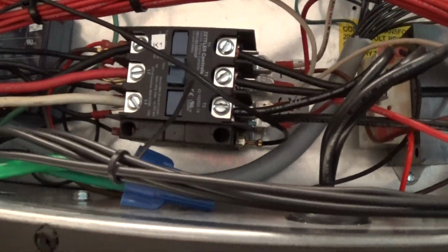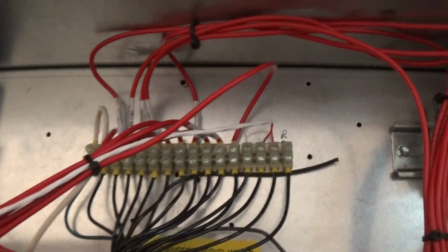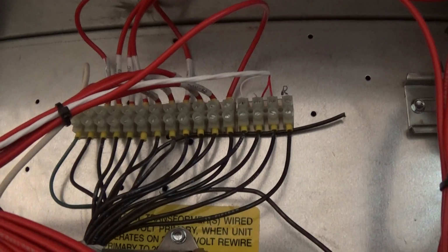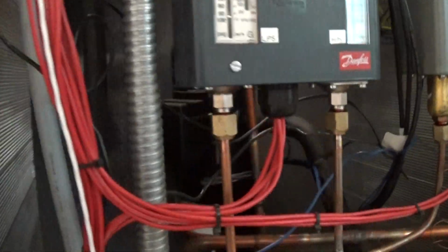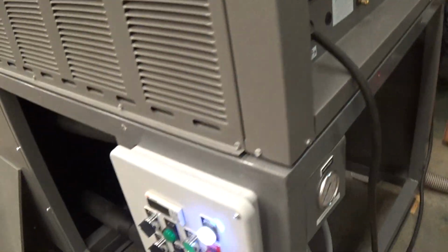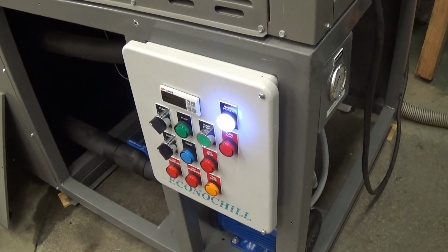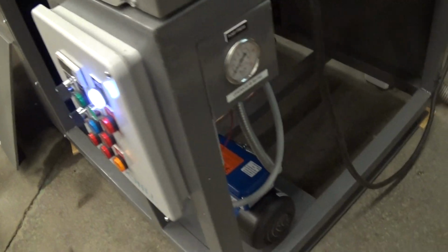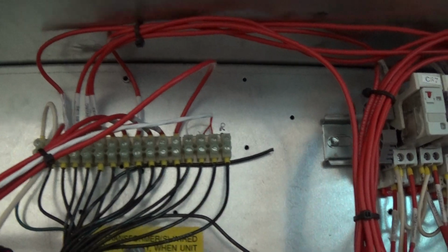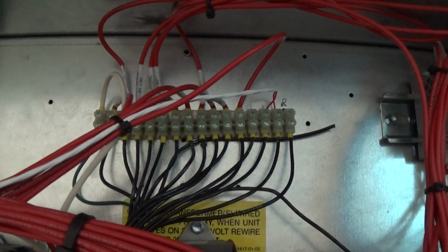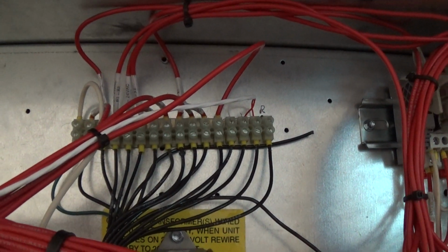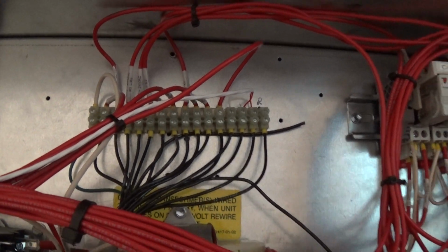That's our main incoming power contactor there, our control transformer. This terminal block here, that's kind of slick. In this case here, or in all cases with our E-Chill, we make it upgradable to mount this controller remotely. So you have this multi-conductor cable that comes from the controller here up to this terminal block, and by just getting a longer cable you can mount that control panel indoors. In this case here it's cabinet mounted, as we call it.